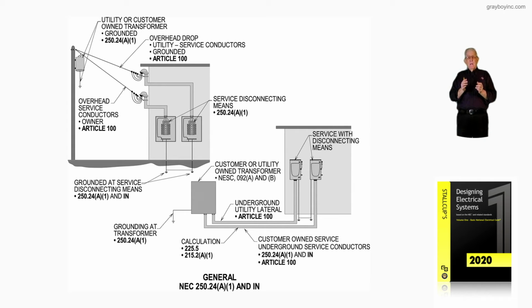and cities. But notice on the other hand, if that was a customer-owned transformer, and the customer put in those conductors and used rigid metal conduit, with no electrical ordinance or utility guideline that said otherwise, they don't have to be 24 inches deep, only 6 inches deep, because they'd be classified service conductors and they'd only comply with Table 300.50 or Table 300.5, depending on the voltage.